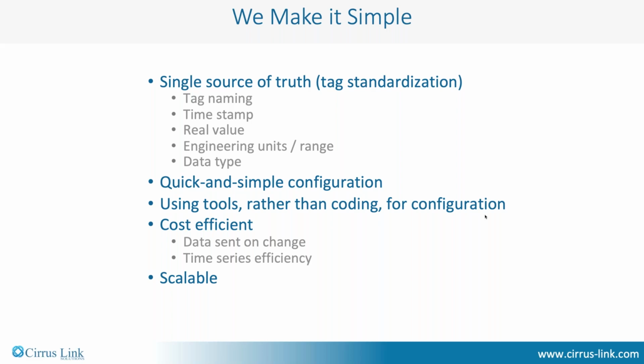So one of the things we do with Sparkplug is standardize tags so that a tag can represent or have a tag name per your system, a timestamp that stays with that tag, the real value of that engineering units or process variable, what are the engineering units in the range, and what's the data type. We make it quick and simple to configure things with tools, not coding on operating systems, but a proper tag browser and the tools that you, as a SCADA or operational engineer, should have available. It's got to be cost effective.